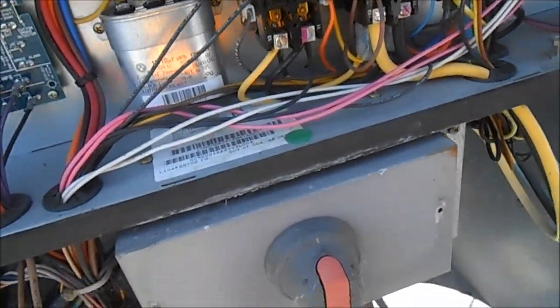The nearest certified technician for these things is apparently like five hours away, so they sent me up here to try and figure it out. Contactors are good. They're not getting 24 volts. The 24 volts is coming out of the transformer, I understand correct.